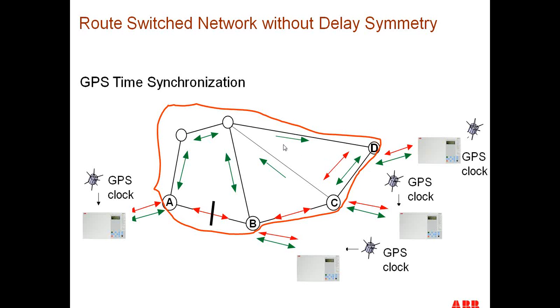But go back to our generic thing again. We have a GPS synchronized signal at each terminal, so it doesn't matter what route it takes to get from one point to the other, bouncing back and forth, as long as we time tag that sample, so that we line up the time tagged samples together and do the comparison at that point, the current differential algorithm. So that's the recommended way of using the relays nowadays, through GPS time synchronization.